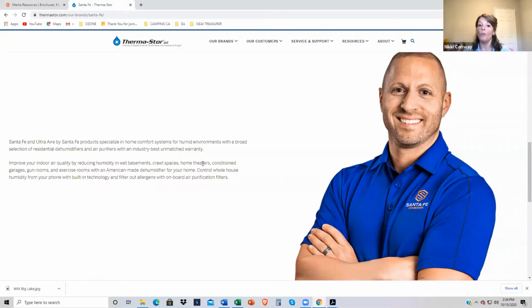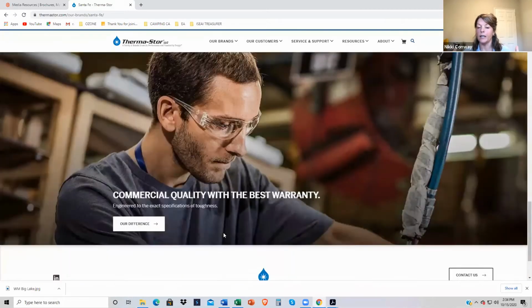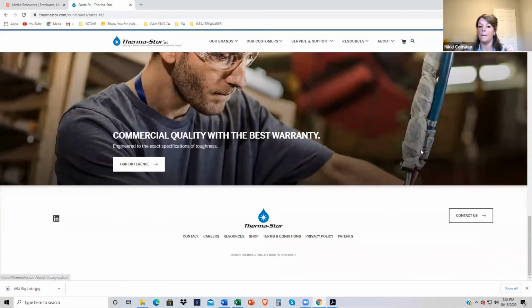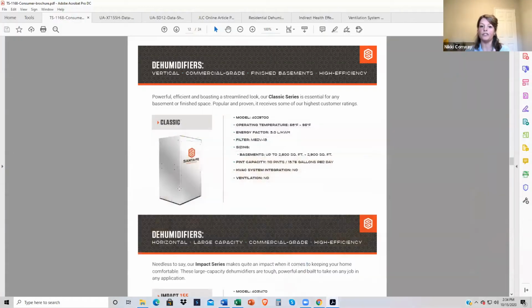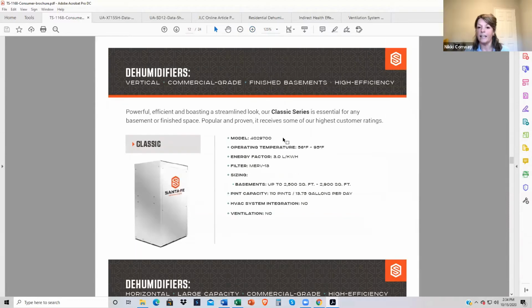Most dehumidifiers, the classic example, like this one rated at 110 pints, that's rated at 80 degrees and 60% relative humidity. That's what the rating system has been for dehumidifiers. So that's basically an indoor pool condition.